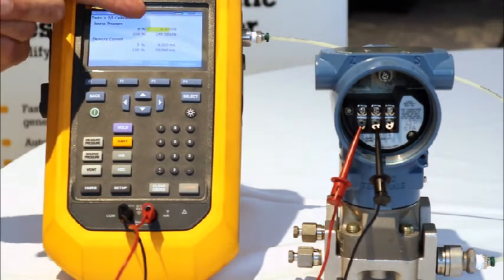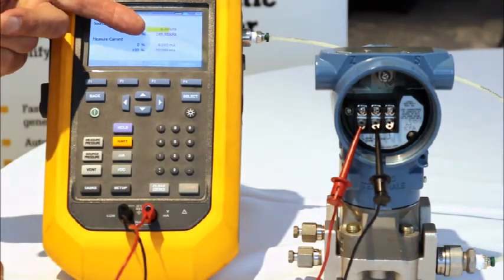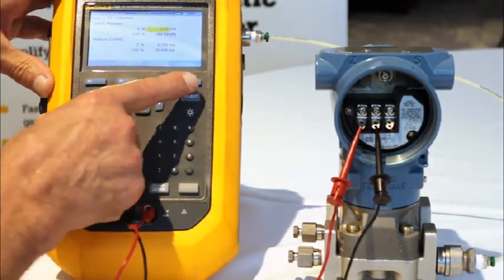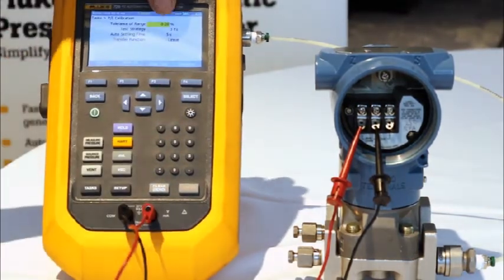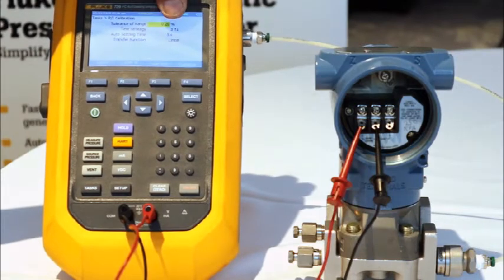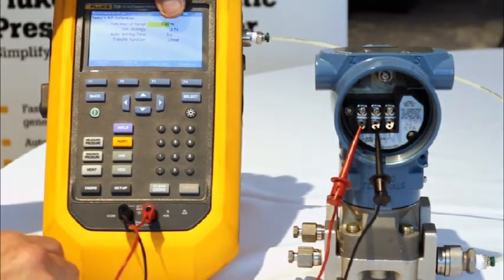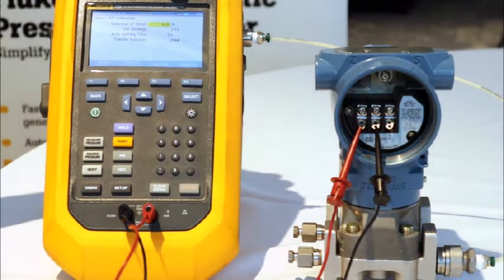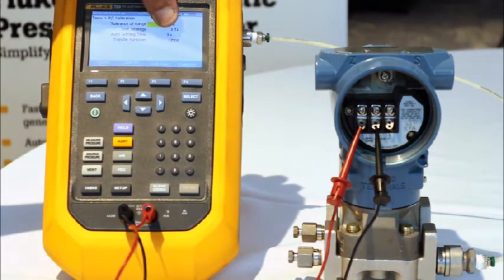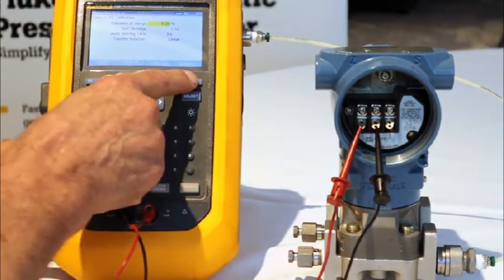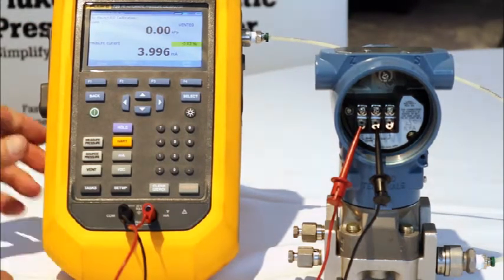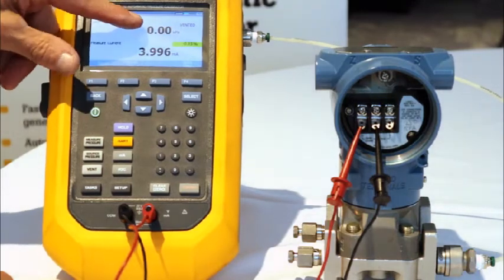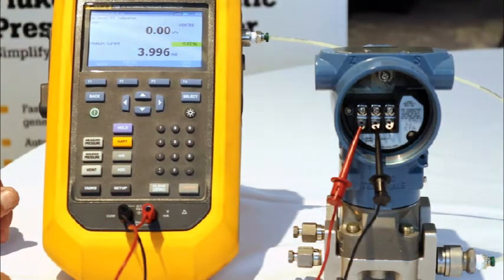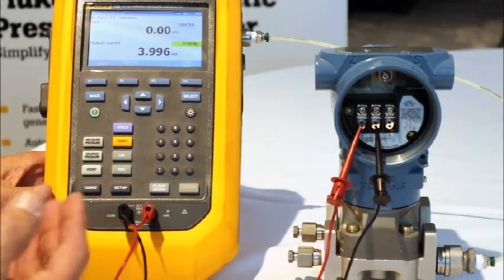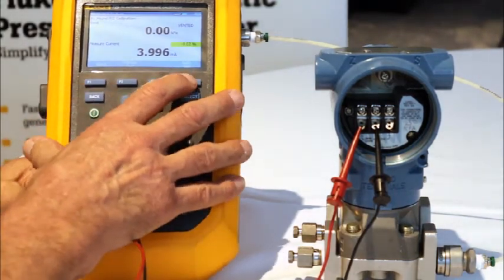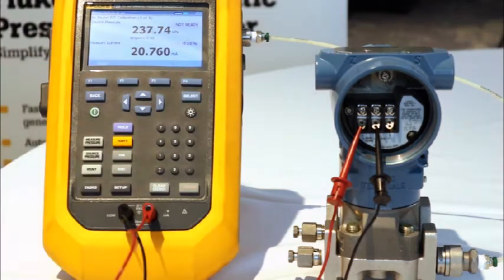So I've identified that this device is 0 to 150 kPa, and we'll measure 4 to 20 milliamps. We're going to test at 0.2%. We're going to do a 3-point up-down test, 0, 50, 100%, and then 50 and 0% of the range of the transmitter. And the calibrator is going to settle for 5 seconds on each measurement step. So continue. Here we can see the current that's being measured and the pressure being applied, which is essentially the first test point since the lower range value of the transmitter is 0 kPa. I select auto test, and the calibrator does the rest.